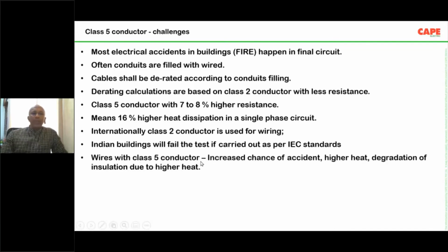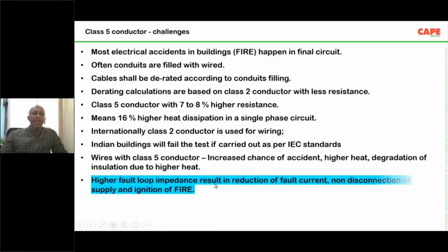So wires with class 5 conductor increase the chance of accident, higher heat dissipation, and degradation of insulation due to higher heat. But the most important point is not the heat. The most important point is higher fault loop impedance. Fault loop impedance means you have a protective device to trip your circuit. The tripping mechanism is related to the fault current which is flowing through the circuit, and the fault current flowing through the circuit is related to the impedance of the circuit.